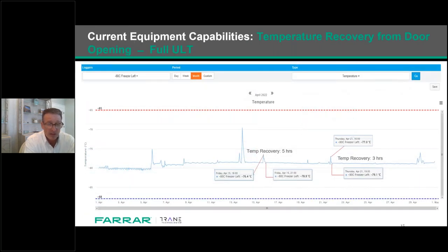When we look at the temperature recovery from door opening, we've covered the refrigeration system capabilities for cold wall and forced air convection system, but let's switch gears to temperature recovery from door opening. As you know, temperature recovery is key to protecting product, specifically for long-term storage. In this graph, this is a standard ULT cold wall freezer. As you can see, the door was opened on April 15th, and the temperature recovery was 5 hours, because you see the spike. A spike usually means when you go from minus 80 to, let's say, minus 72 or minus 76 real quick, that's a door opening, because temperature just doesn't fluctuate that widely.